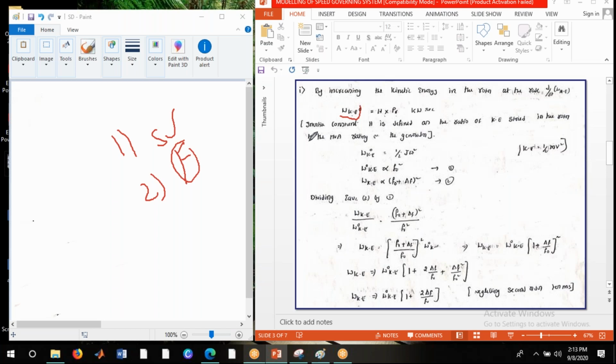So based on how much rotating speed is happening in the generator, the real power will be generated with respect to the inertia constant. Based on the inertia constant, the rotor will be rotating in the free condition. The inertia constant H is defined as the ratio of kinetic energy in the rotor to the MVA rating of the generator. So this is given by H.